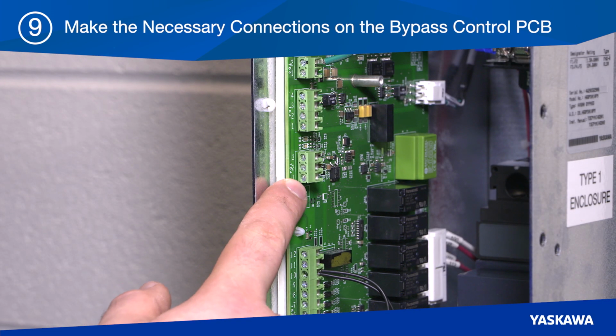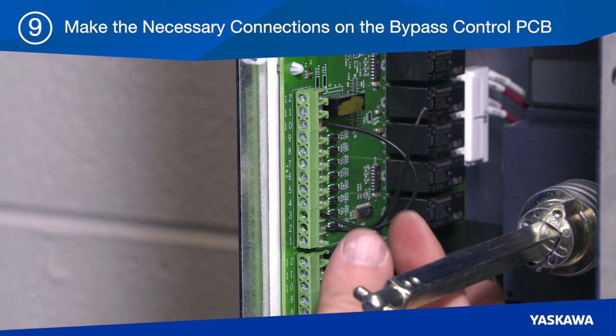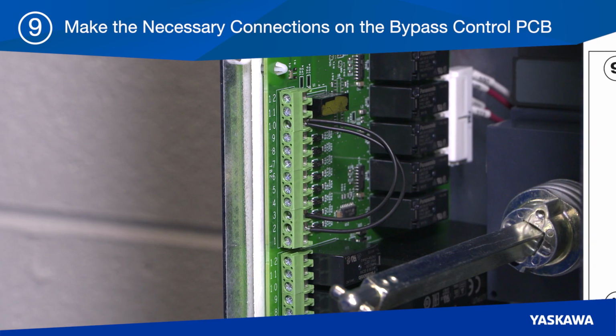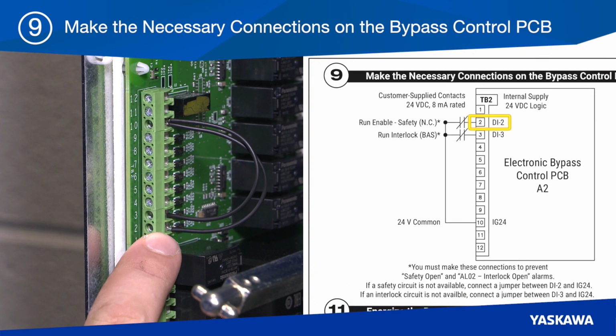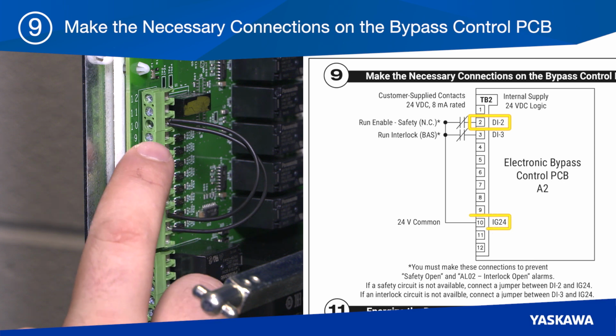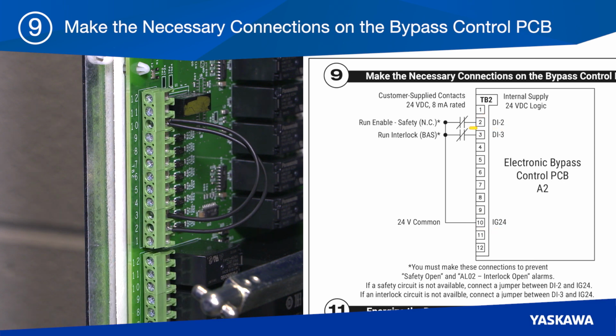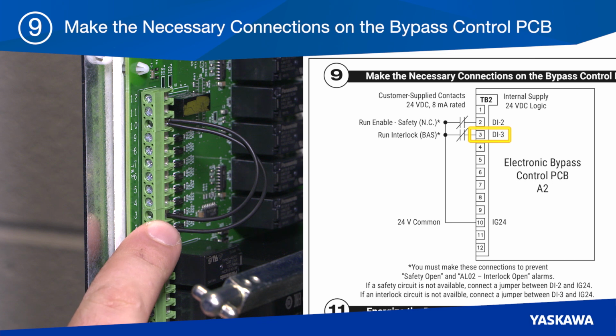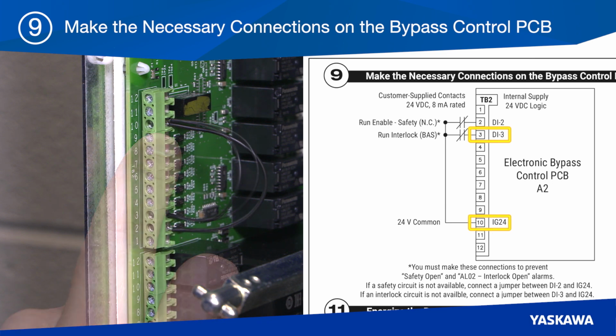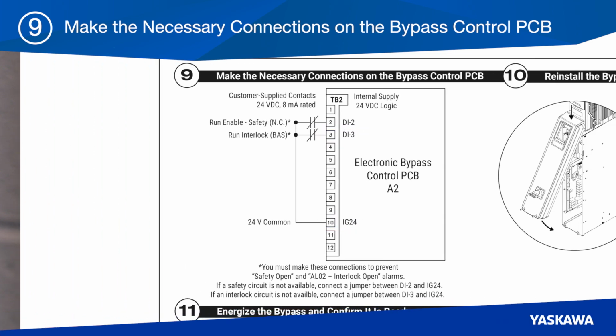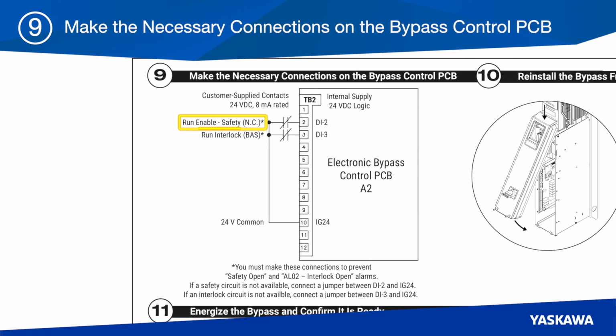If external wiring is not available, install customer-supplied jumpers between bypass control PCB terminals TB2 2 and 10, and between TB2 3 and 10. These jumpers make the run enable safety and run interlocks and allow the bypass to run in hand while avoiding safety open and interlock open alarms.